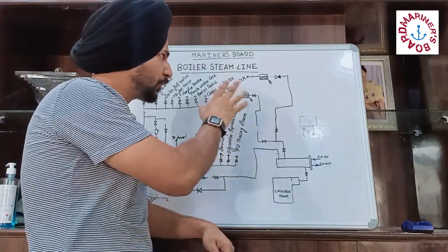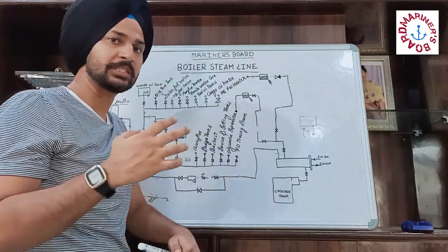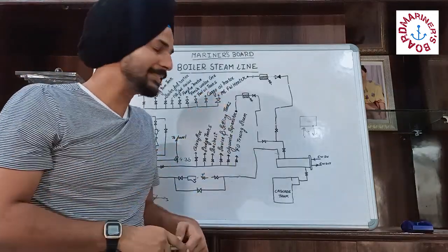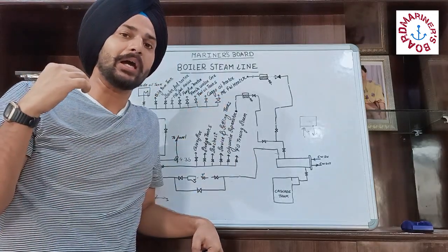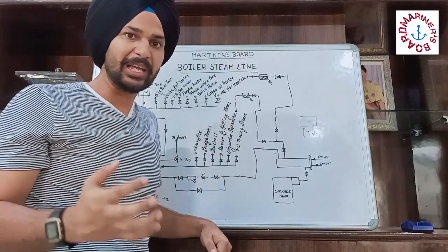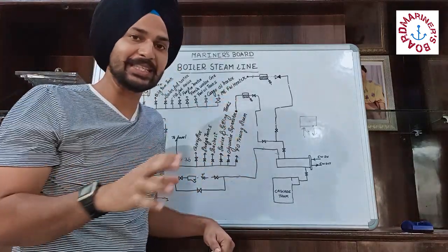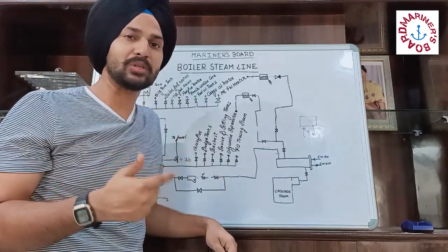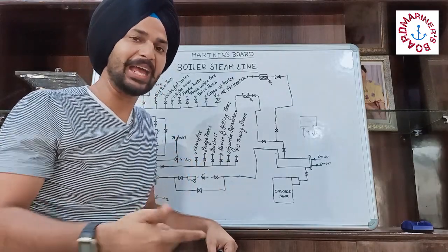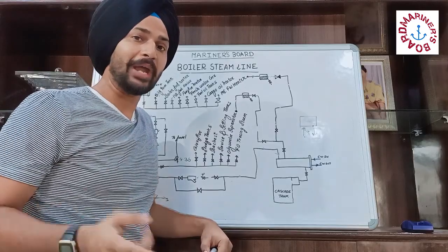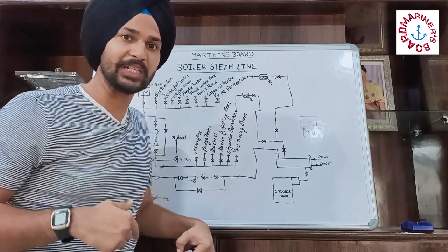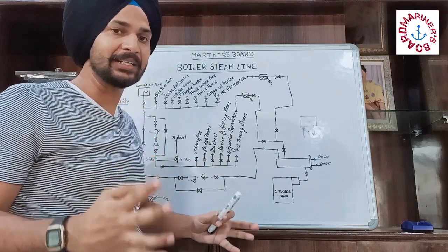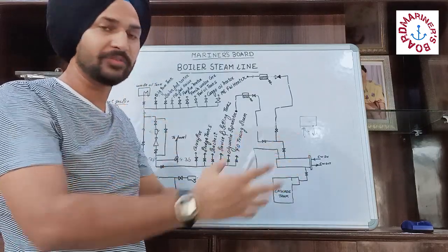For now, the only thing we should know is the purpose of the steam trap. The steam trap allows the complete utilization of the steam inside the tank, so that the steam that comes out does not come out as steam but as condensate. And when does the steam get converted into condensate? When it gives all its latent heat to the content of the tank.